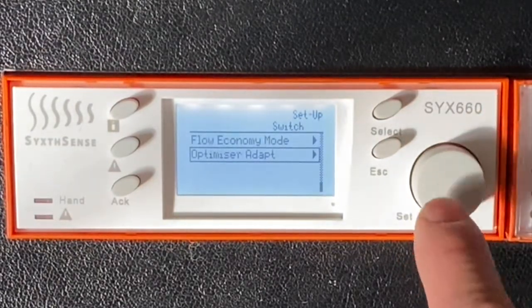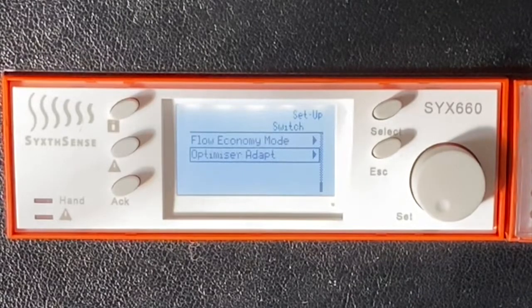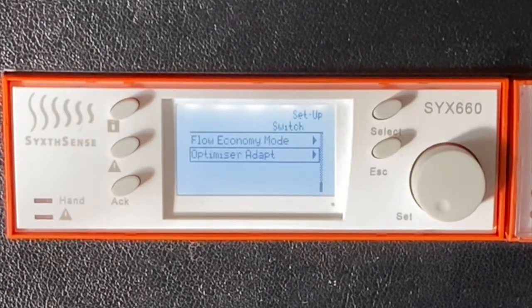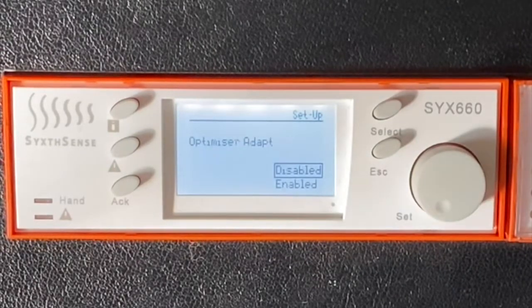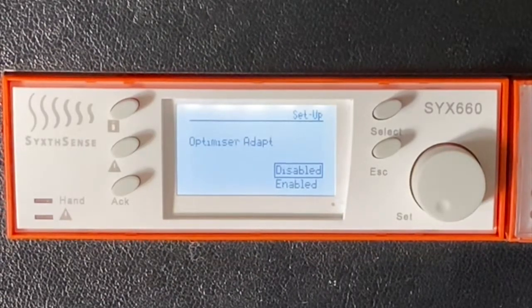Optimizer adaptation, we'll come on to this when we talk about the optimizer low limit alarm. There's a separate video on that, but in this particular case we want the optimizer to remain adapted. We don't want to disable it at this stage. We want the optimizer always to be enabled wherever possible, and we should understand the system dynamics to make sure that the optimizer is working as efficiently as possible.